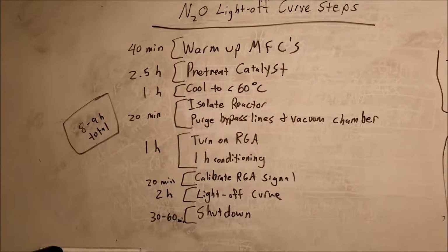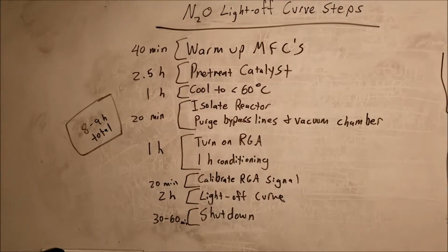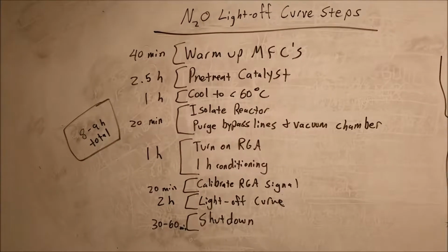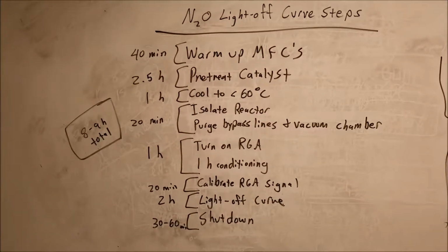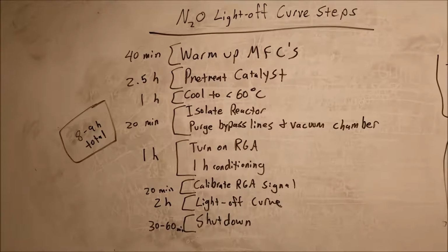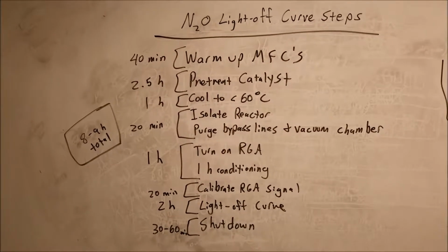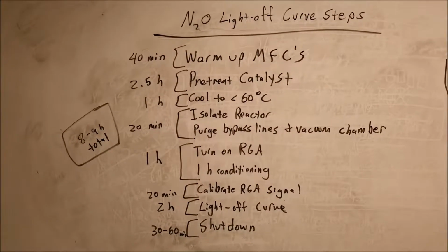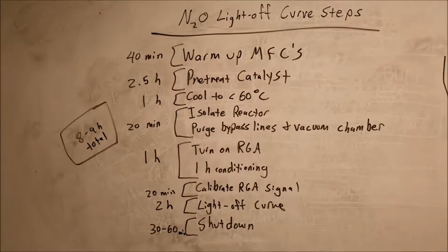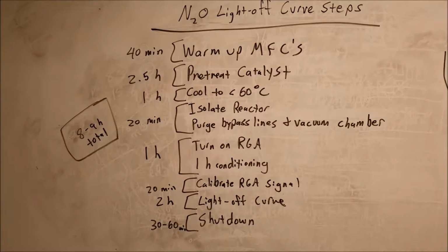If you get to the end of the test, the first sample point is supposed to be at 40 degrees. And so if we get to the end of the conditioning and we're, say, at 45 degrees or 43 degrees, and you don't want to wait the last 30 to 60 minutes for it to cool down, you can just use 50 degrees as your first sample point.